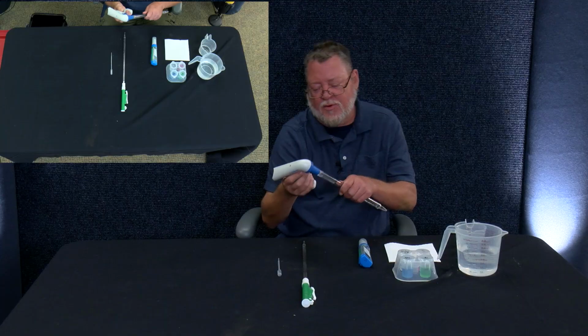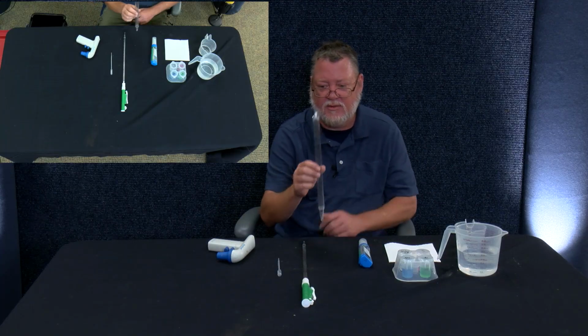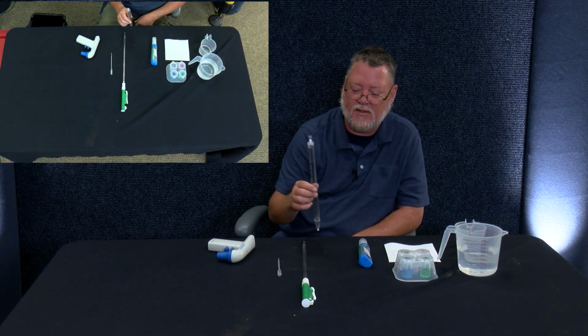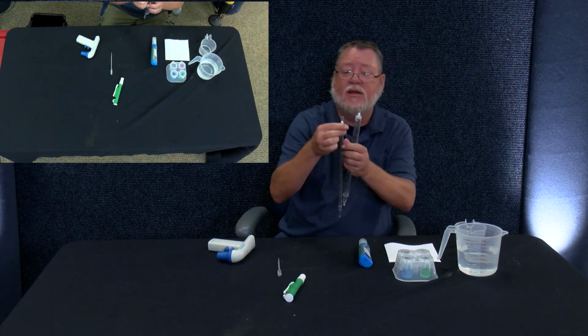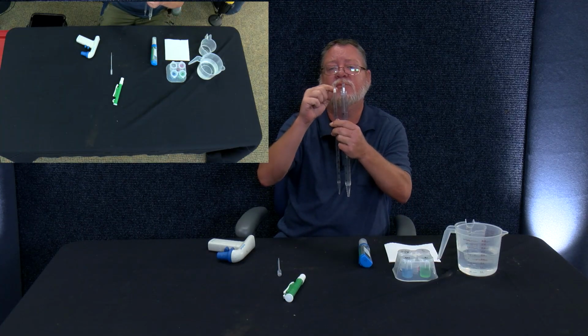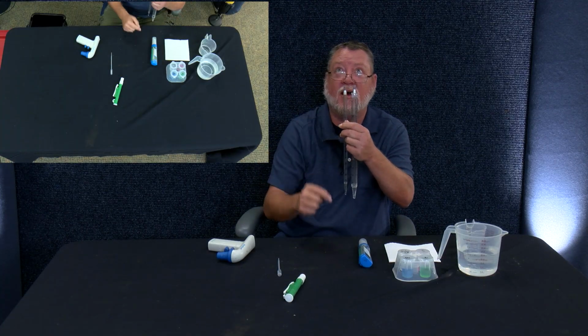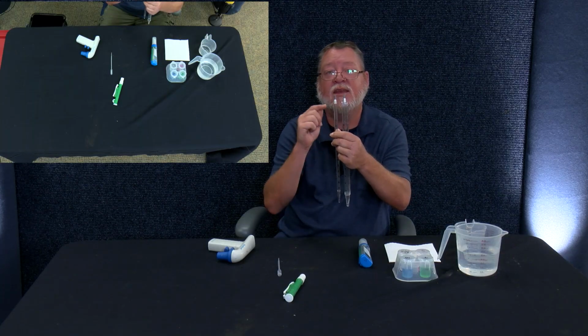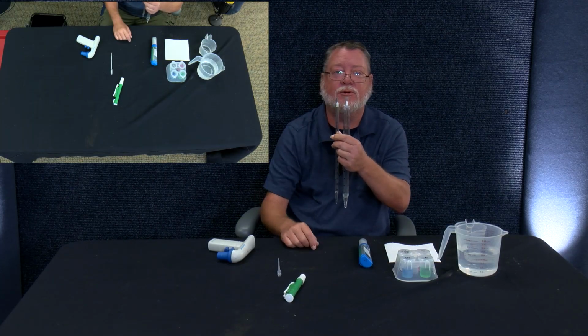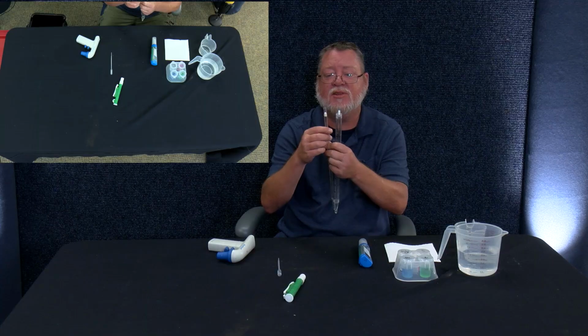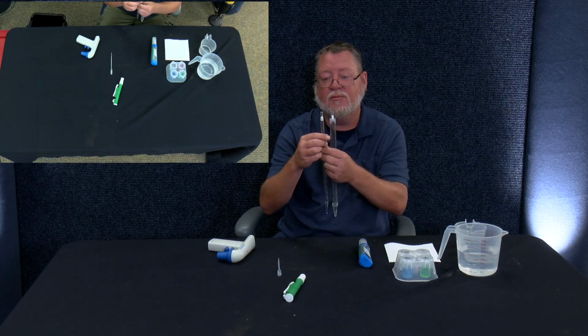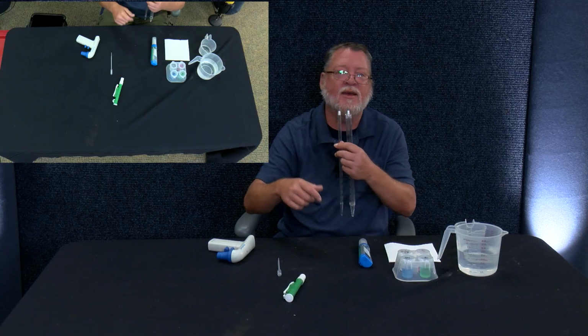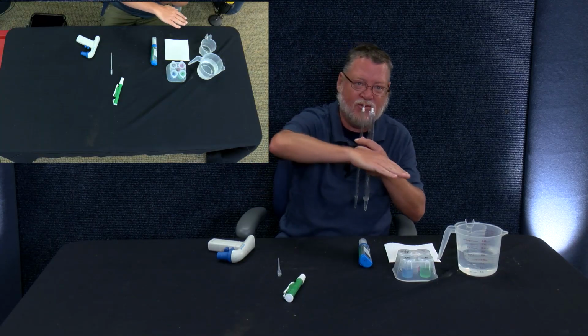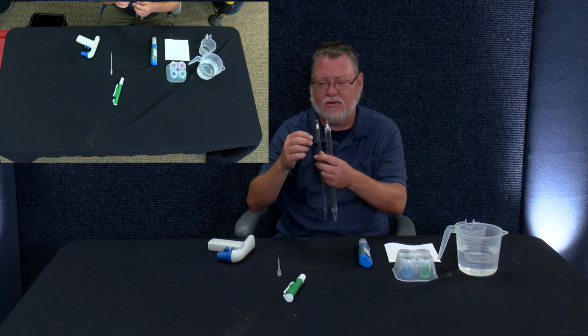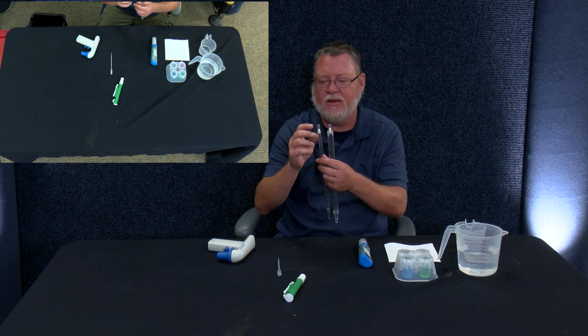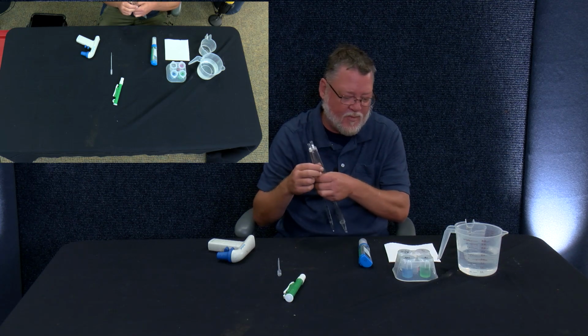Now, the most important part about these pipettes, both of them actually, is you can see there's a little piece of cotton at the top, right? And if that gets wet, you have to throw it away. So you have to keep that dry at all points in time. So don't store them upside down. Always leave them on an incline, so that way the moisture stays away from that cotton.